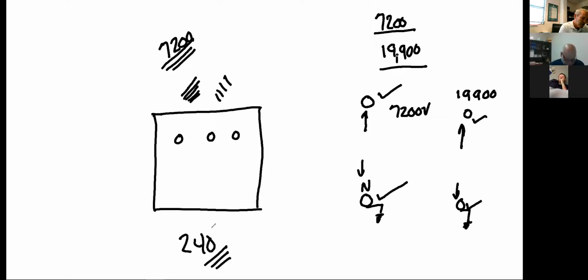That's the great indicator right there, letting you know what's going on as far as the voltages are concerned with this transformer. You're just going to see 1 to 30 a large amount of times, that's our main distribution voltage right there. You're going to know that from here on out, 7,200, 240 to a home is a 1 to 30 ratio. It's just going to come to your mind automatically, all the time. What you need to look out for is, well, what if I change my voltage to 480? Say I need to use this on a pump or something, I need a higher voltage, then you're going to have to compute that. Okay, so going back here, let me start with a fresh screen.